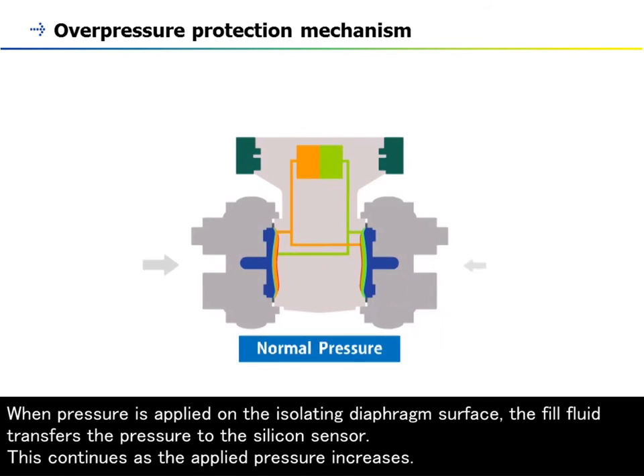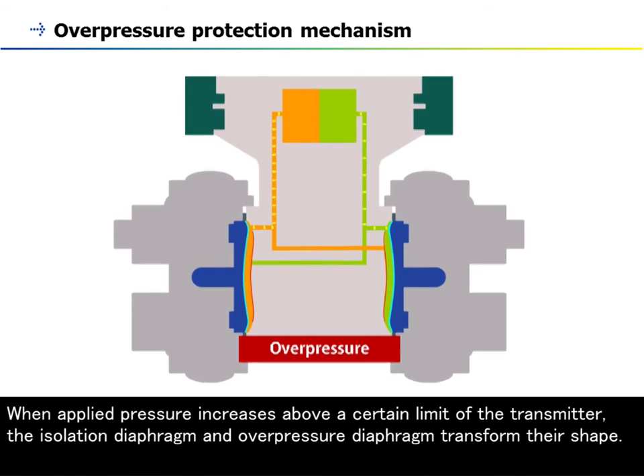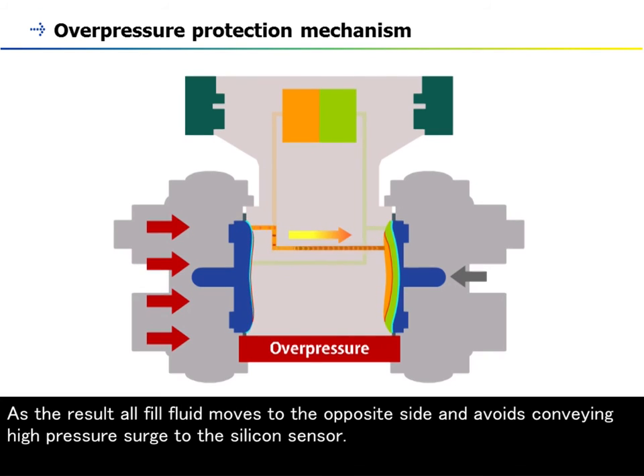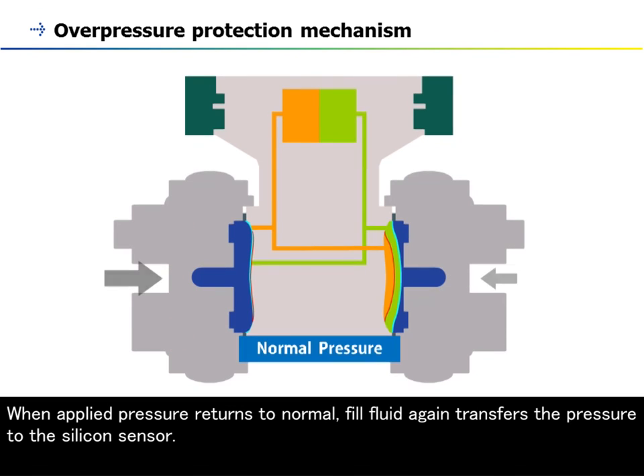When pressure is applied on the isolating diaphragm surface, the fill fluid transfers the pressure to the silicon sensor. This continues as the applied pressure increases. When applied pressure increases above a certain limit of the transmitter, the isolation diaphragm and overpressure diaphragm transform their shape. As a result, all fill fluid moves to the opposite side and avoids conveying high-pressure surge to the silicon sensor. When applied pressure returns to normal, fill fluid again transfers the pressure to the silicon sensor.